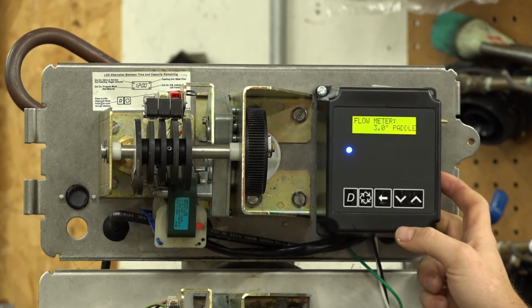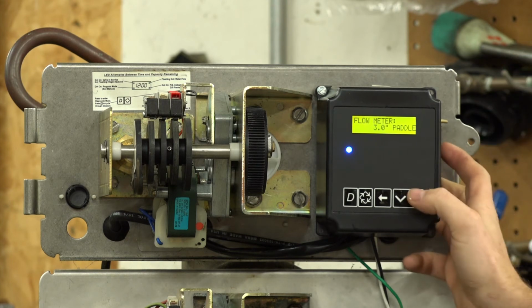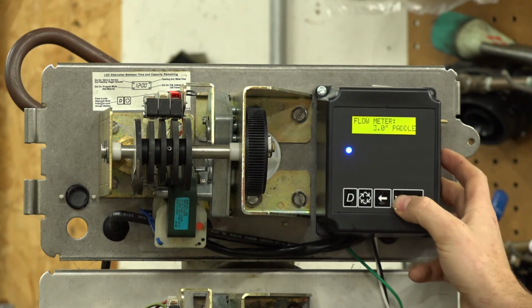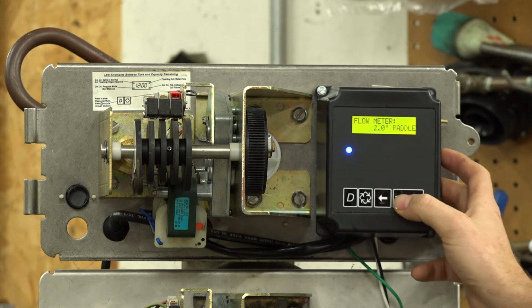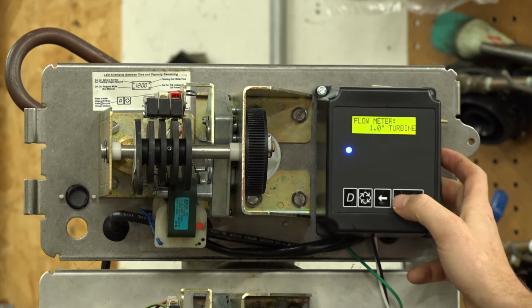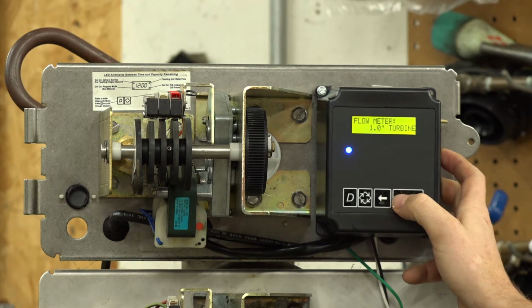Right now it says flow meter 3-inch paddle. It's a 3-inch valve. Typically you have a 3-inch meter with it. Where this becomes important is you've got 2-inch, you have a 1.5-inch turbine, a 1.5-inch paddle, 2 different meters that Pentair manufactures. So what is a paddle? The standard meter, the ones that you would think of from a Pentair standpoint, with the meter dome on top and the brass body, those are all going to be paddle.